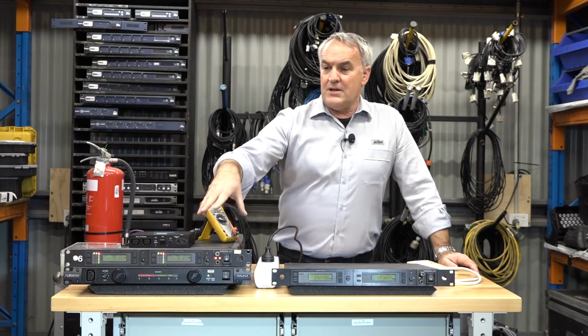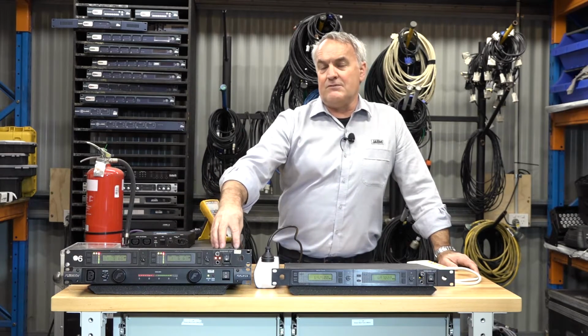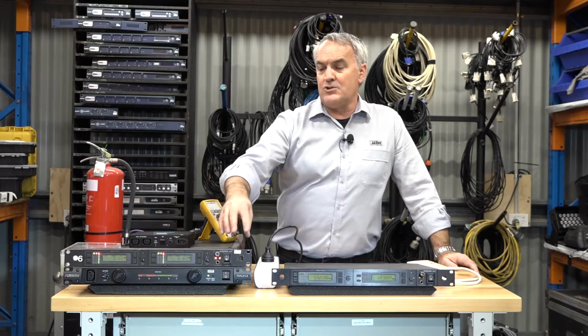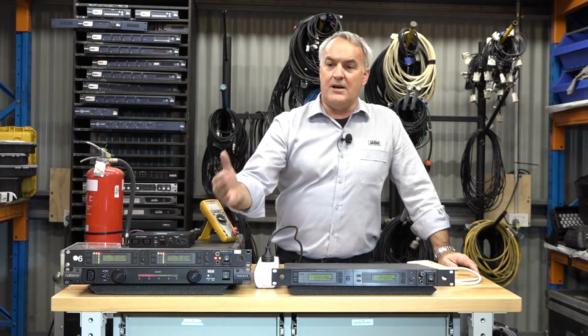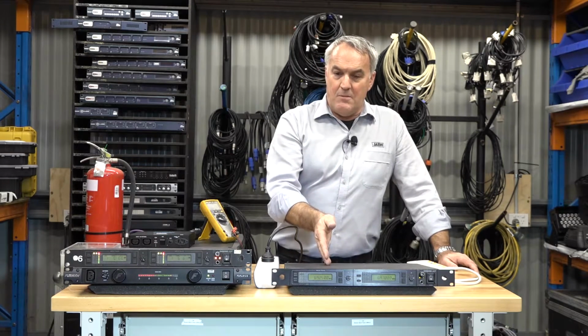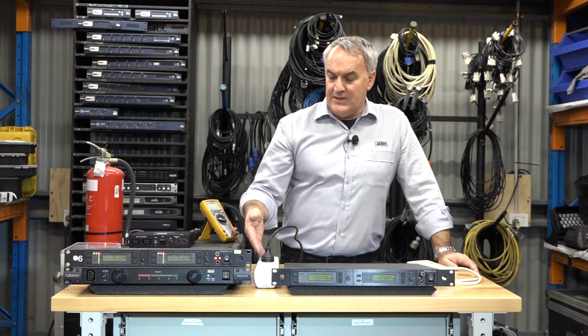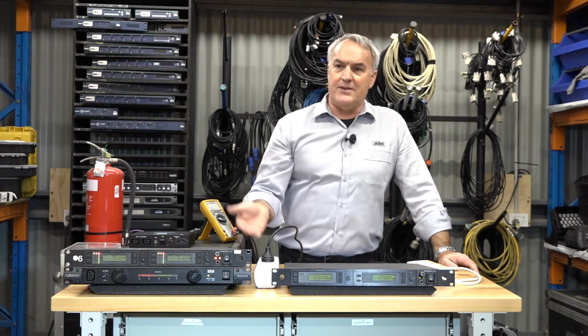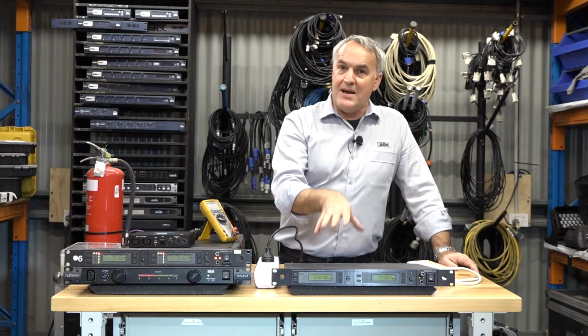The one on this side, once the Furman detects a mains voltage of over about 270 volts, should disconnect from the line to isolate it. The one on this side, what will happen is the MOVs in this power strip will attempt to shunt that energy away, but it'll remain on.